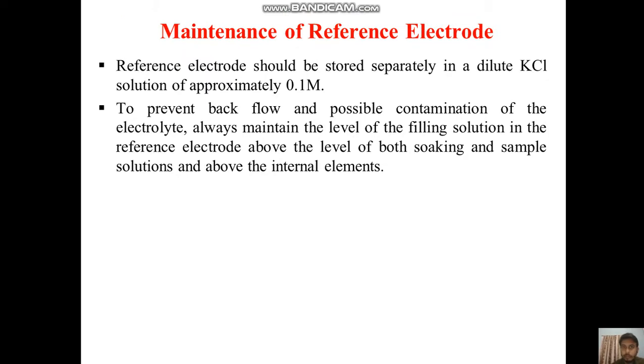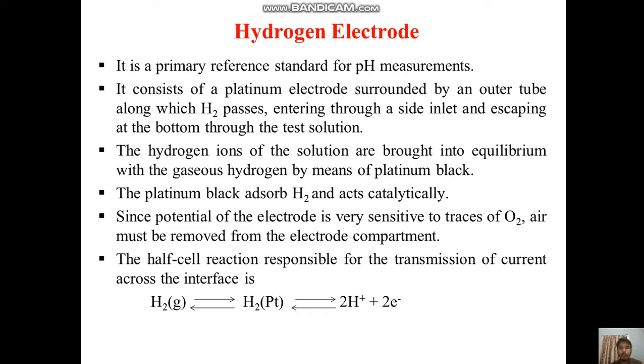For the maintenance of these reference electrodes, they should be stored separately in a dilute KCl solution of approximately 0.1 molar to prevent backflow and possible contamination of the electrolyte, and always maintain the level of the filling solution in the reference electrode above the level of both the sample solution and the internal elements.